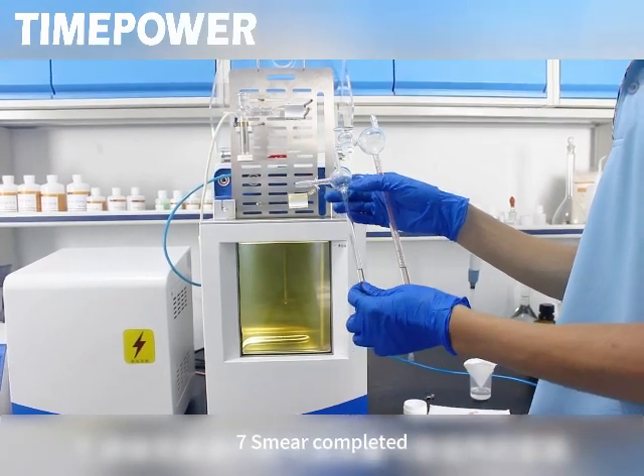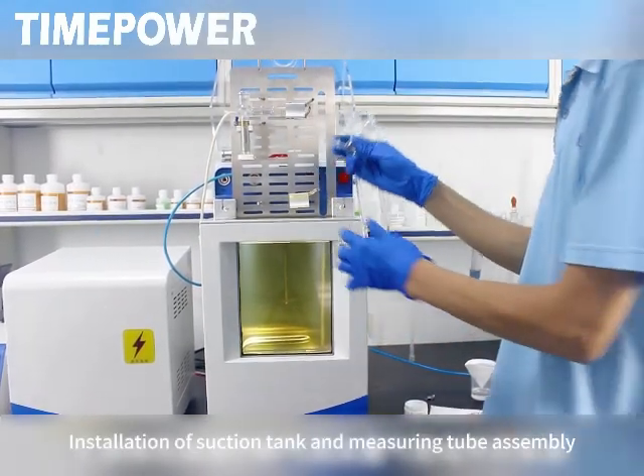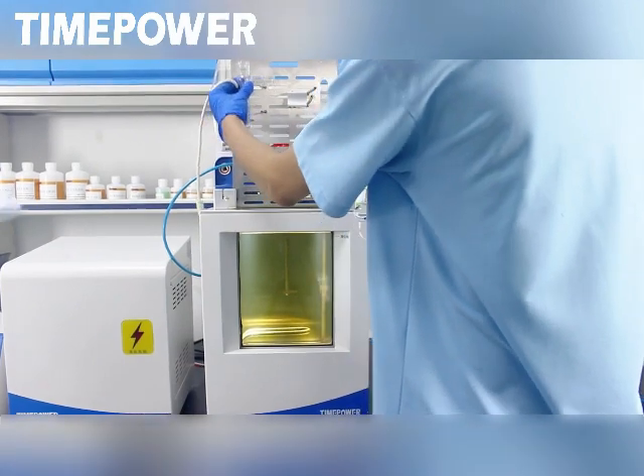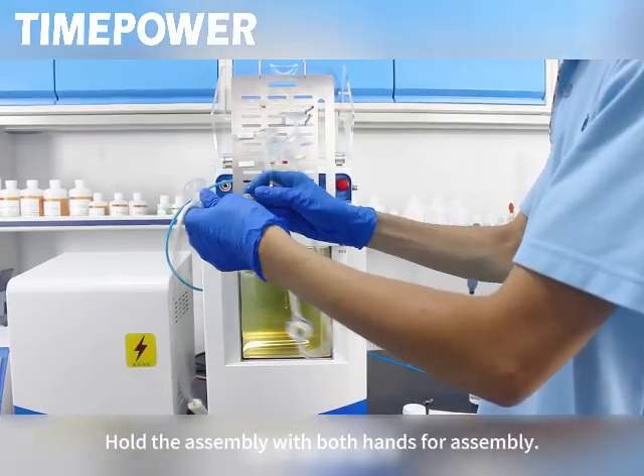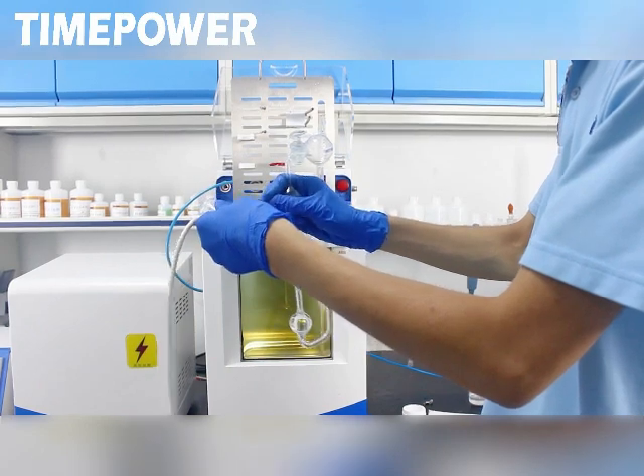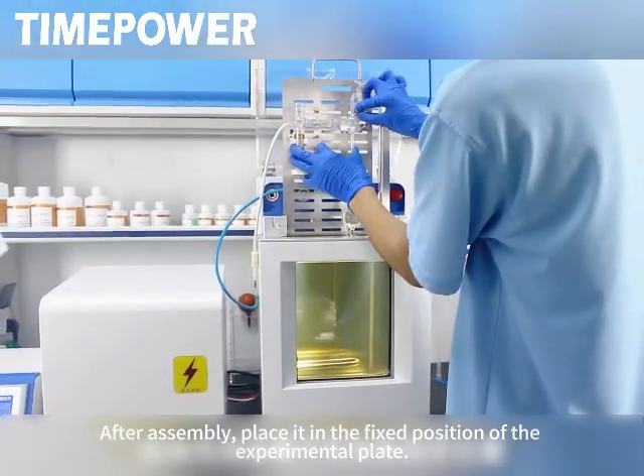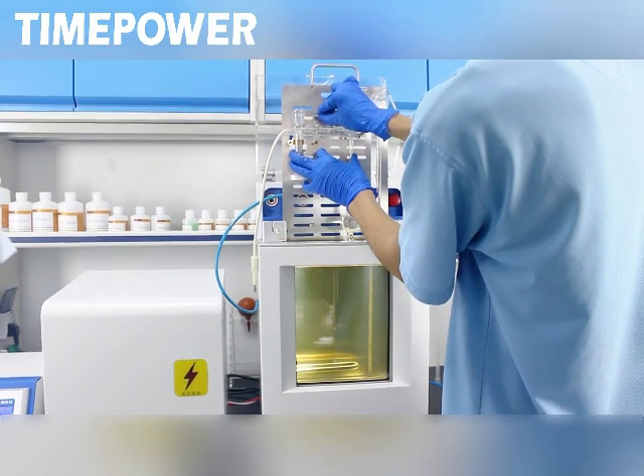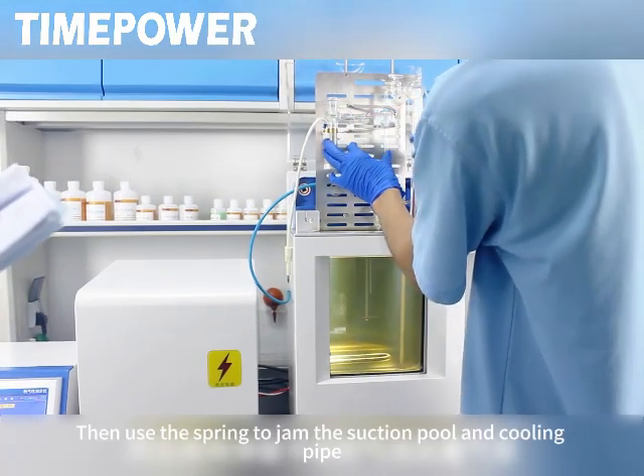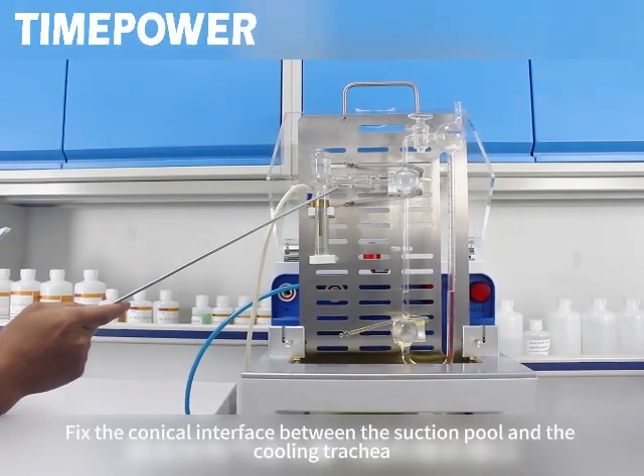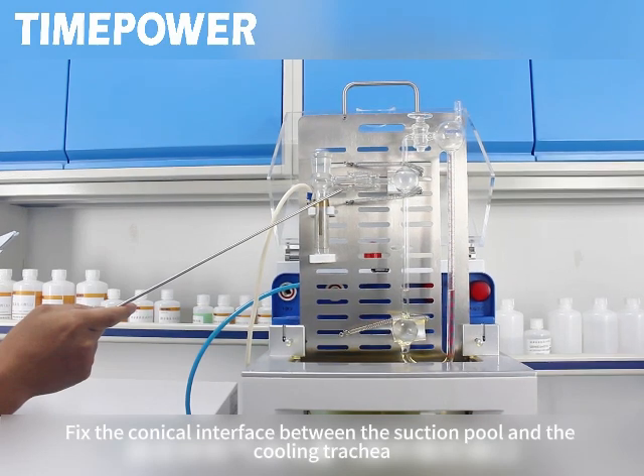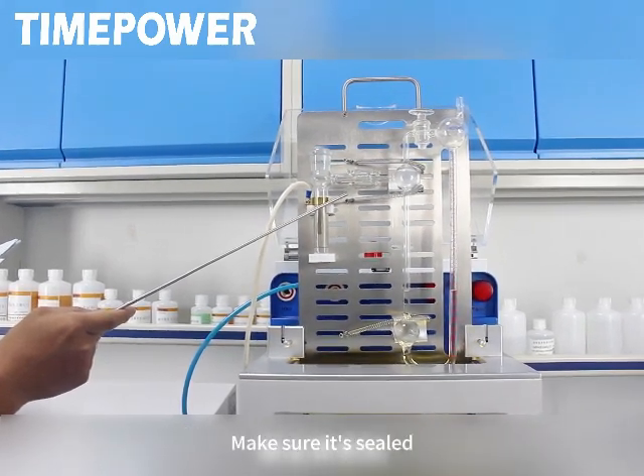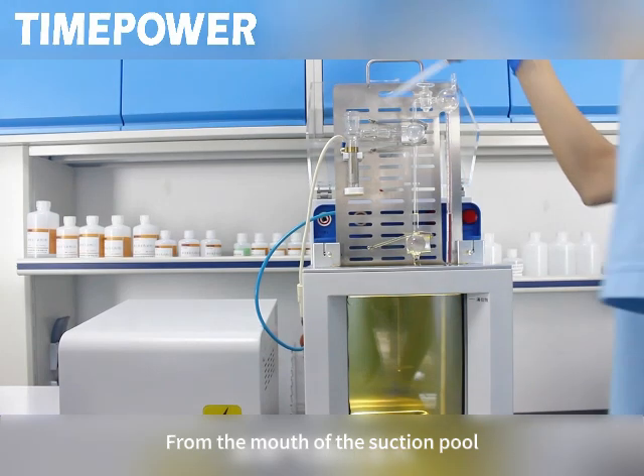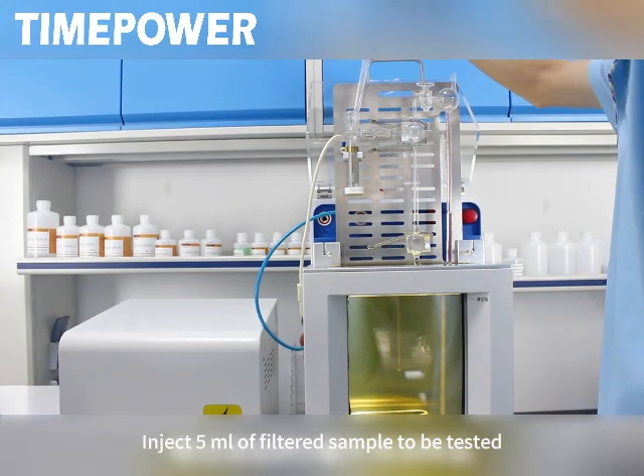7. Smearing completed. Install the suction tank and measuring tube assembly. Hold the assembly with both hands for assembly. After assembly, place it in the fixed position of the experimental plate. Then use the spring to jam the suction pool and cooling pipe. Fix the conical interface between the suction pool and the cooling trachea. Make sure it's sealed. From the mouth of the suction pool, inject 5 milliliters of filtered sample to be tested.